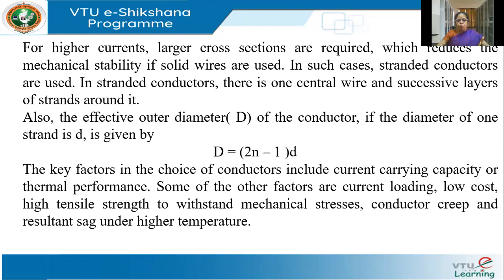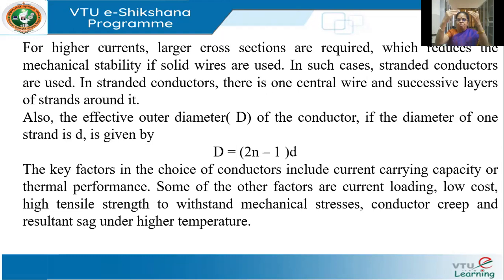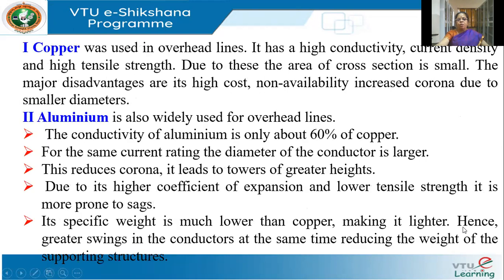When you choose a conductor for an overhead line, you look at the current carrying capacity, thermal performance, current loading, cost, and tensile strength — it has to withstand tension due to wind, ice, or snow. All these mechanical stresses the conductor must be able to withstand. And sag — a line because of its weight will sag, just like a clothesline sags when you hang clothes on it. All these are important when choosing the material for the conductor.